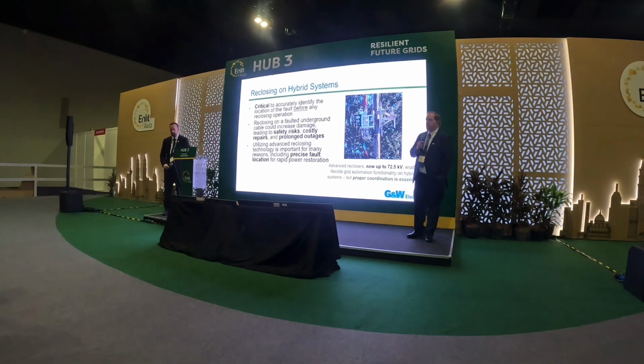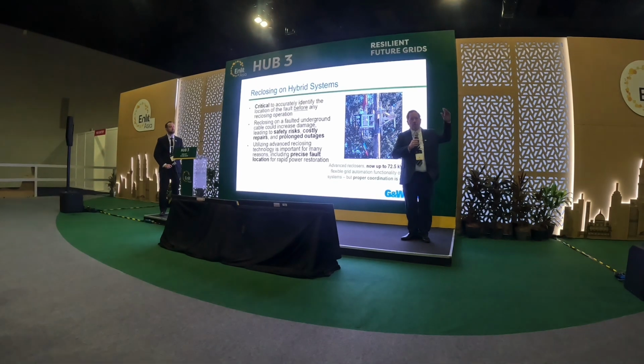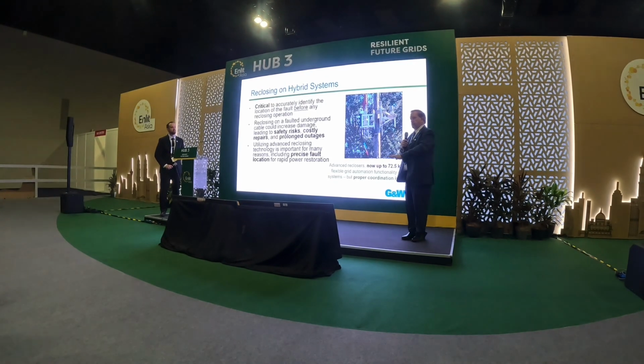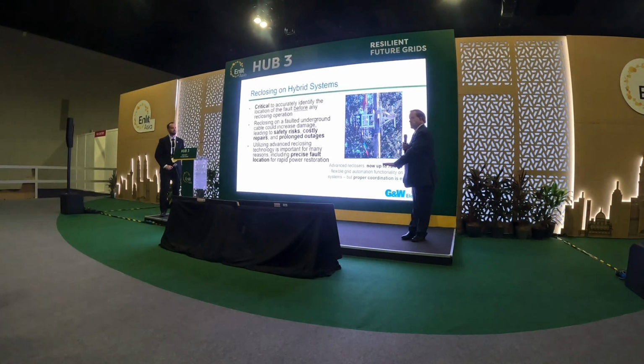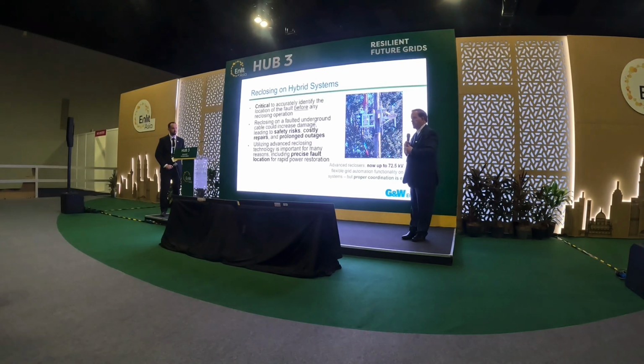So when you're reclosing and you have a hybrid system, meaning you have overhead lines and then you have underground lines, you do not want to reclose on a fault that's under the ground. This is, as Kyle mentioned, right? This is a very bad idea. We're going to talk about that.